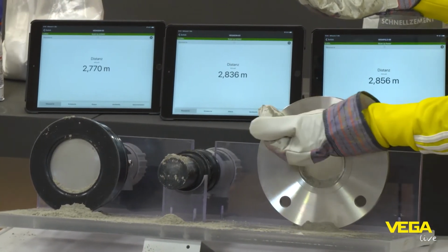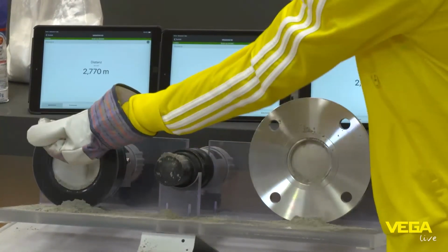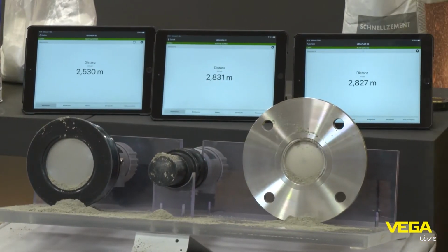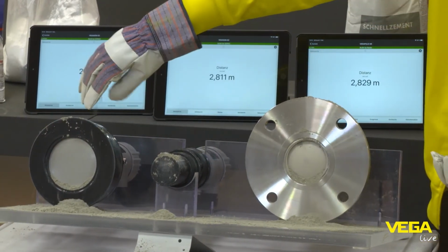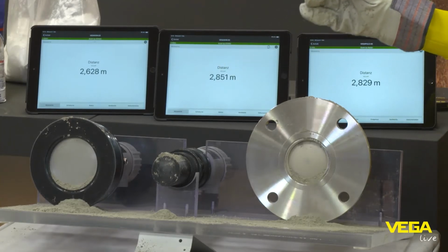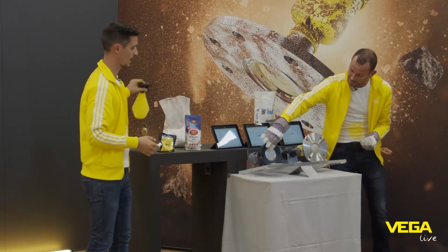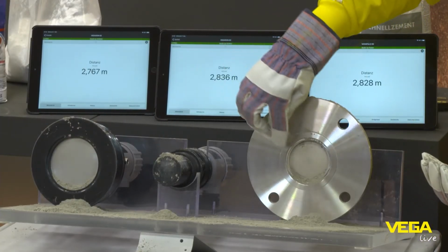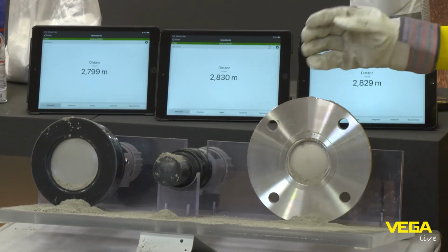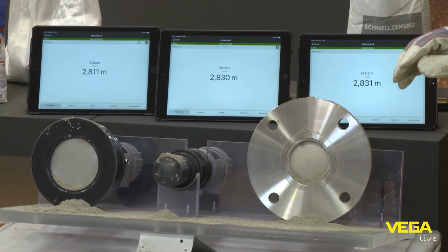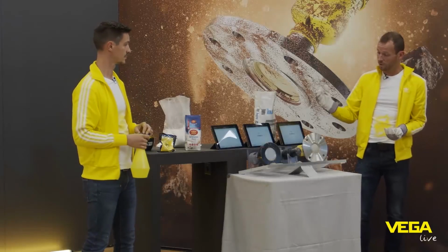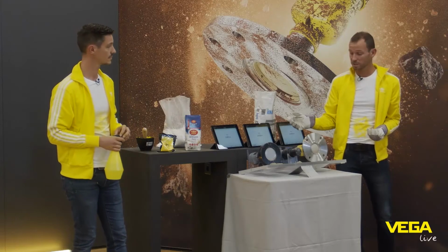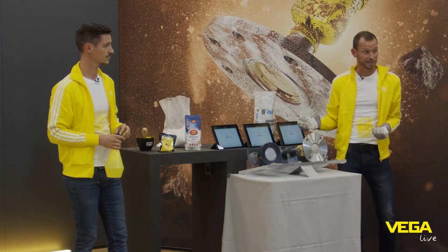Yeah, it's not sticking to the device. You see the most build-up is falling down. So there's a little bit of build-up now on all sensors, but it's not really much. The slight build-up we have on the Vegason 63 here, slight build-up here, and a little bit also here in front of the radar device. And don't be scared, for all of these devices you see they still have the same measurement. So it's not a problem for all of these devices.